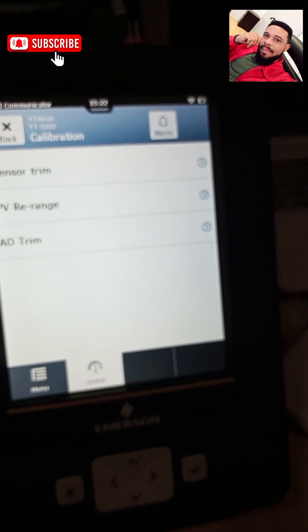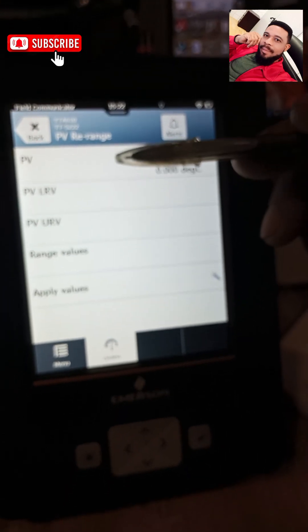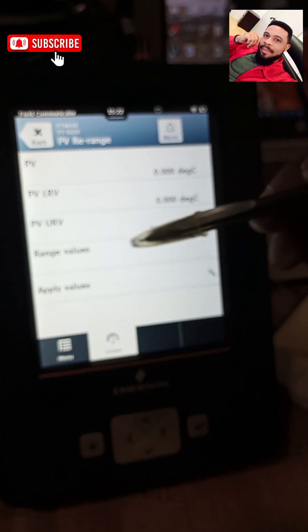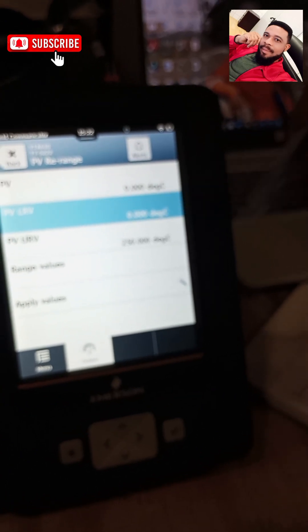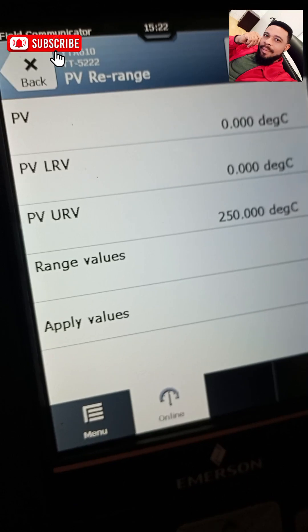Under calibration I have sensor trim, PV range (process variable range), and current trim. If I want to re-range, I go to PV re-range. I have my lower range value and my upper range value. Currently my lower range value is zero and my upper range value is 250 degrees. I don't intend to tamper with these changes, so I'm going to apply those same values.